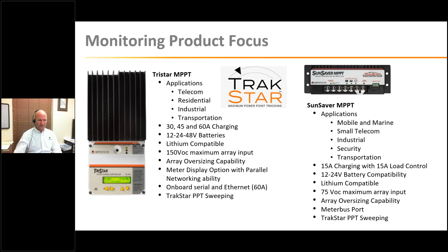Even the SunSaver MPPT, a much smaller model, has the TrakStar tracking algorithm. Its applications include similar uses plus mobile and marine, smaller telecom systems, point-to-point radios (not so much cellular), industrial, security, and transportation, which are growing immensely in volume. It has 15 amp charging and 15 amp load control, 12 and 24 volt batteries, lithium compatibility, a lower but still highly useful 75 volt open circuit maximum input, array oversizing capability, our meter bus port, and the TrakStar technology.